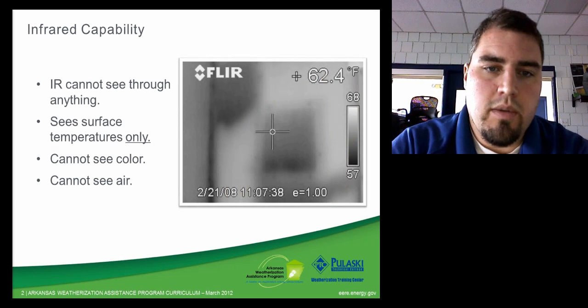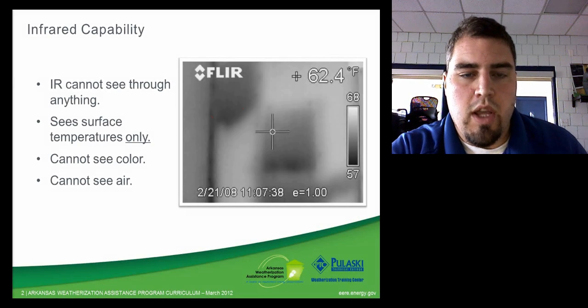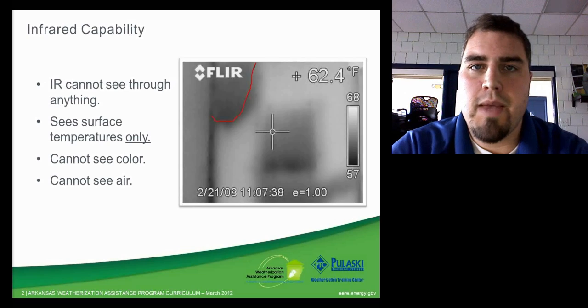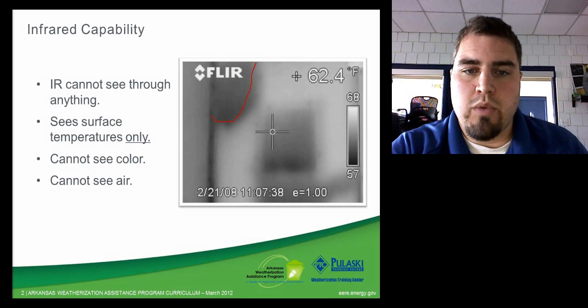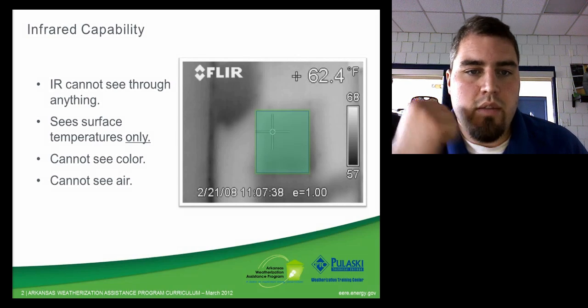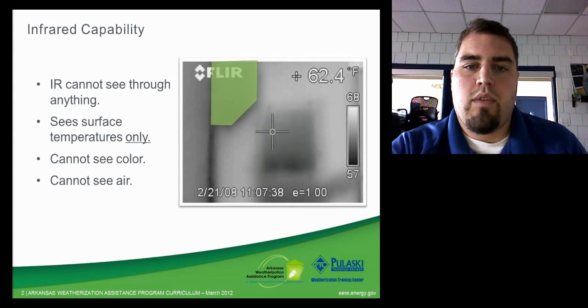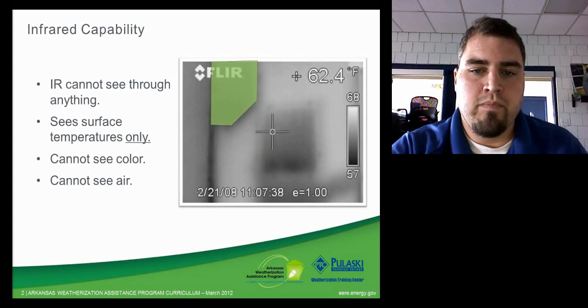Okay, the darker portion here on the nicely insulated wall is where they loose filled that bay and the insulation settled down, so we're seeing the void of insulation there and the cold air where it's making its way through the wall. So we'll see the window there highlighted in dark green, and then the insulation void highlighted there with the pea green.